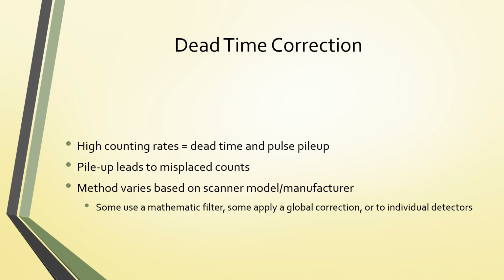Dead time correction is another very important correction. All the PET scanners are susceptible to dead time because they have really high counting rates. Part of that is because you can use a higher dose to the patient with PET, but the patient still gets a lower overall radiation dose than a lot of general imaging procedures. So you also need to give a higher dose because of the really short half-life. And then also because of the short half-life and it's decaying very quickly, you have more counts coming off of the patient than you do with something with a longer half-life.